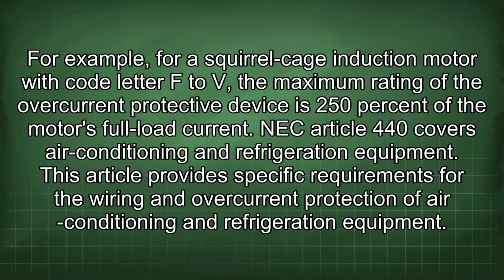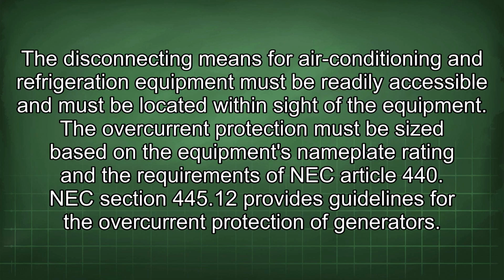NEC Article 440 covers air conditioning and refrigeration equipment. This article provides specific requirements for the wiring and overcurrent protection of air conditioning and refrigeration equipment. The disconnecting means for air conditioning and refrigeration equipment must be readily accessible and must be located within sight of the equipment. The overcurrent protection must be sized based on the equipment's nameplate rating and the requirements of NEC Article 440.